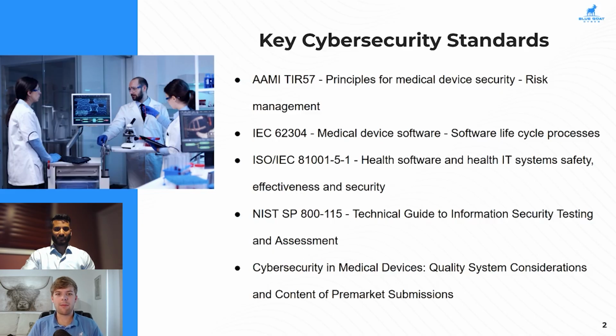First, we're going to look at AAMI TIR 57, the Principles for Medical Device Security Risk Management. This is closely tied into safety risk management for ISO 14971. They have a lot of points for intersection where we're evaluating the combination of safety and security risk, which is a natural evolution just due to the fact that these are medical devices where there is always going to be a little bit of that cross-section.